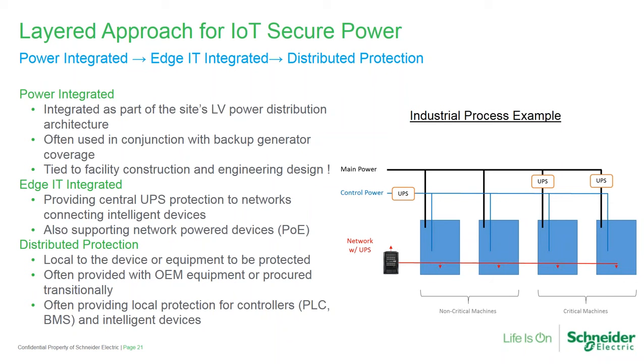If you look at the graphic, we're showing an industrial process example where I have 4 machines in blue, but some machines are deemed non-critical and some critical. For the critical machines, we're providing a UPS to back up the main power, but we're also showing a separate control power connection. This power isn't providing any muscle to the system—no motors, drives, or magnetics. It's just the brains of the system and the devices it's controlling. In this case, the example shows a centralized UPS to provide those systems.